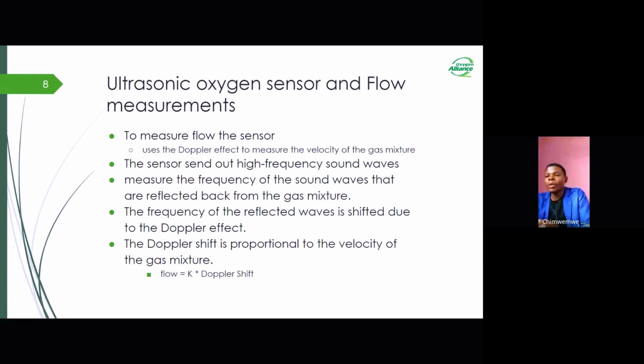So some sensors may use frequencies in the range of 25 kilohertz to 200 kilohertz, while others can go up to the megahertz range. If a gas is in motion, such as flowing through a pipe, the moving gas molecules cause the ultrasonic waves transmitted by these transducers to experience a change in frequency due to the Doppler effect. This change in frequency is proportional to the velocity of the gas. So this change is directly proportional to the flow rate of the gas.